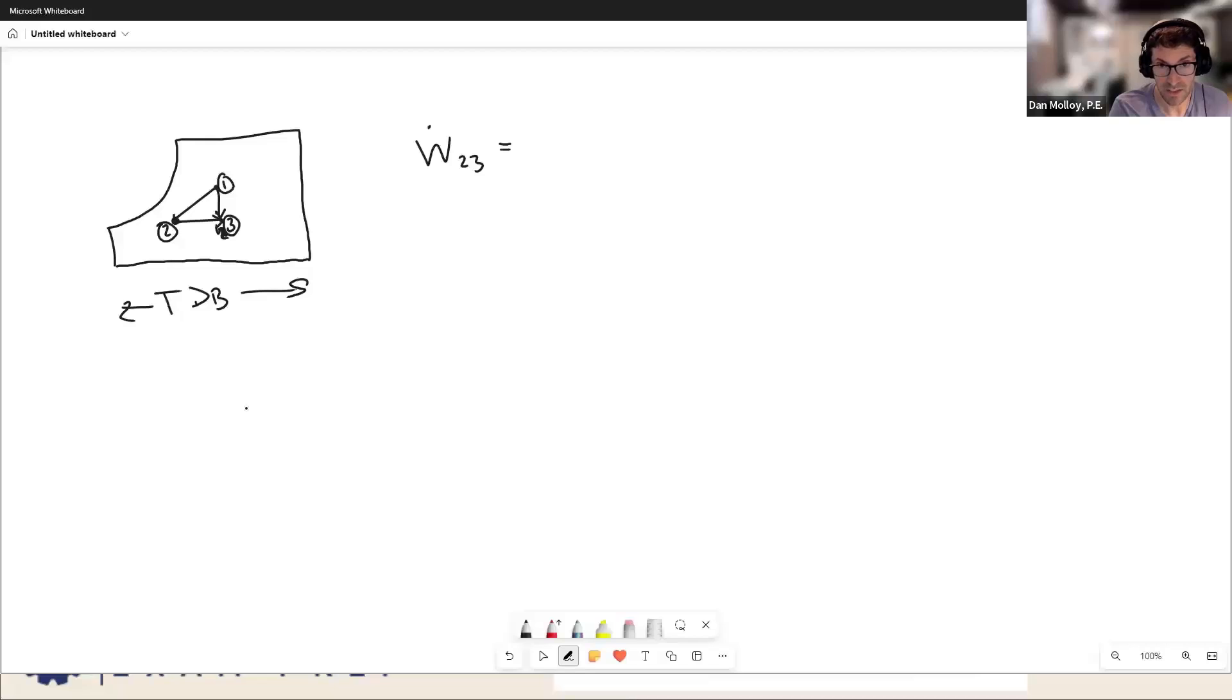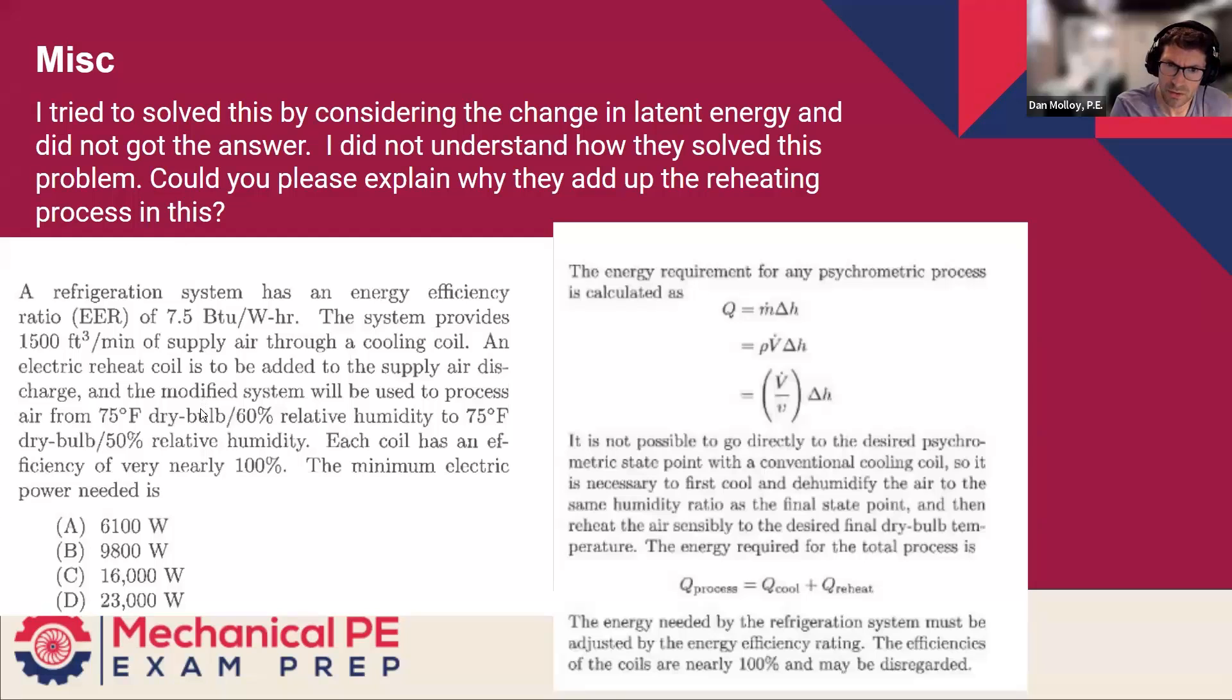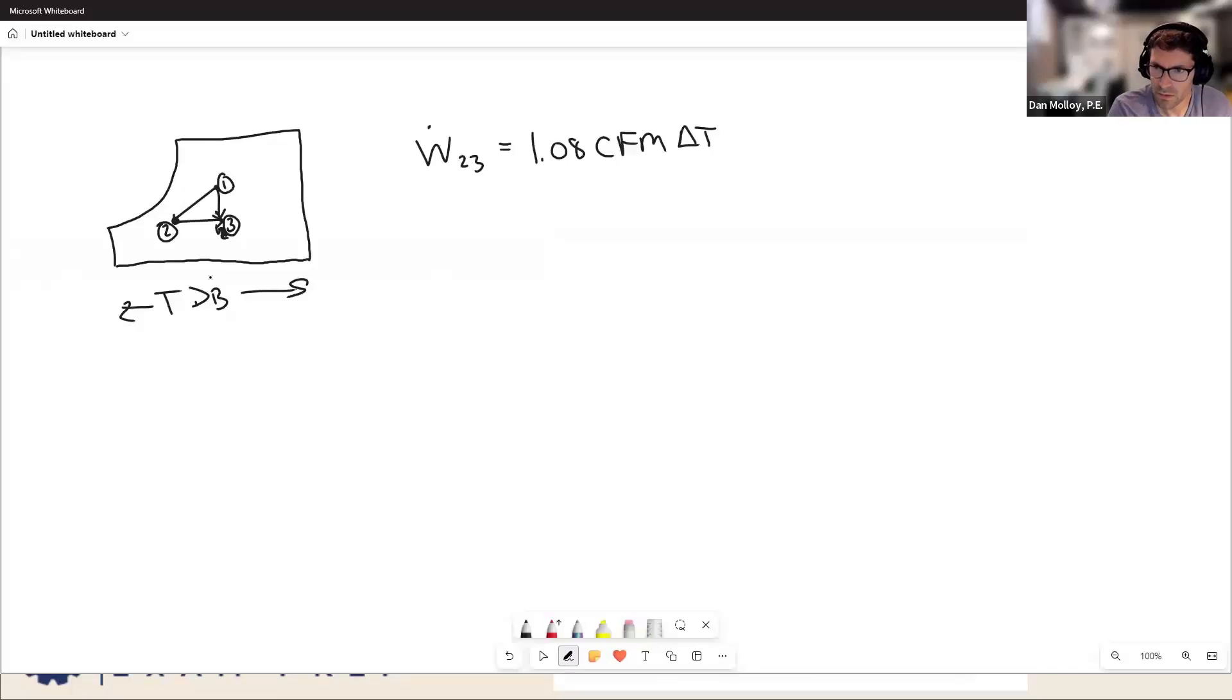That's literally just the amount of heat that's being added. So that's going to be a 1.08 CFM delta T situation. And we know the delta T, because we know the temperature at two and the temperature at three. Does it give you the temperature two off the coil? No, it doesn't. So we'll have to intuit that some other way. We know the COP. We don't know the temperature at state two. All right, let's hold that thought. T3 minus T2, where T2 is a little bit of a question mark.